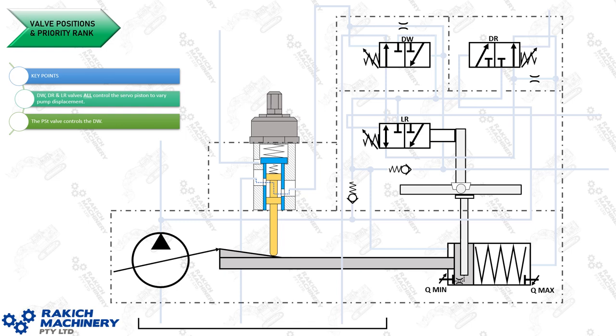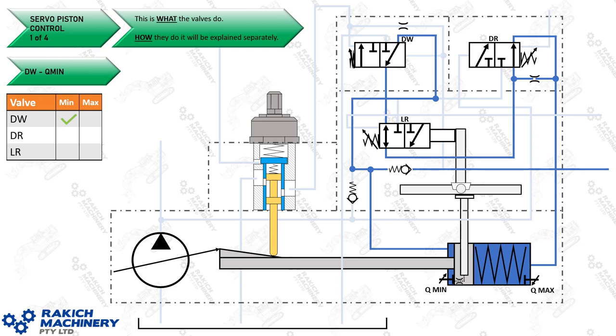Now I'll build on the previous slides and show what the valves are actually doing in their Q-min or Q-max position. Explaining the DW valve: it's now shown shuttled over to the left against the spring. The servo pressure is coming in from the right past this check valve. Note that there is a constant servo pressure supply to the left-hand side of the servo piston — it's always trying to send it to Q-max. That pressure is always there and doesn't rely on any valve positioning to change that.